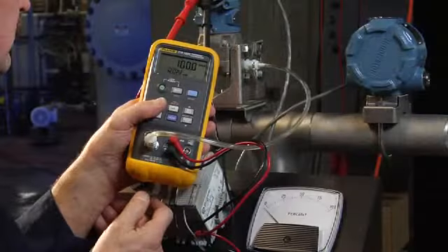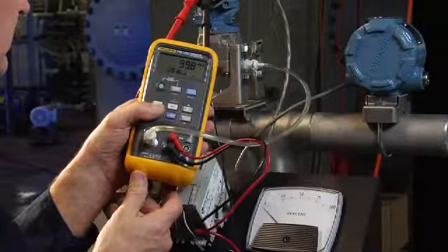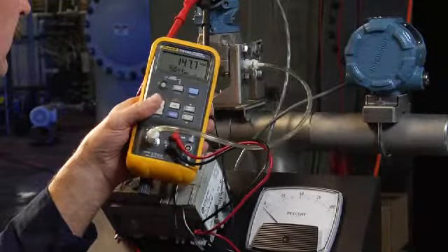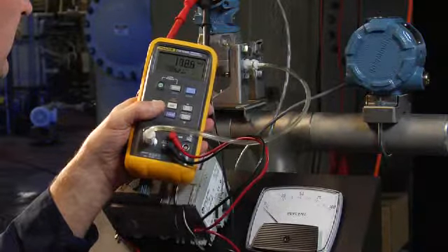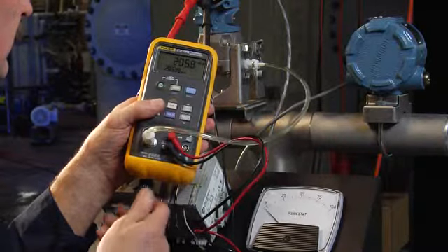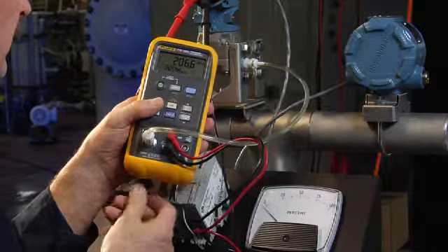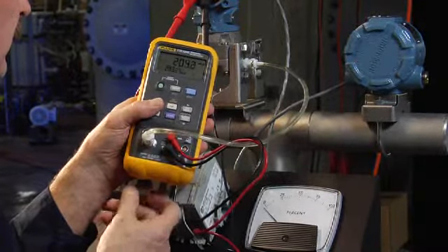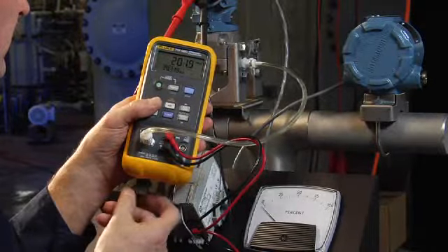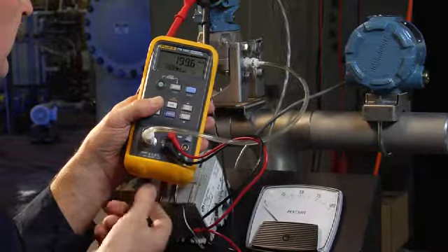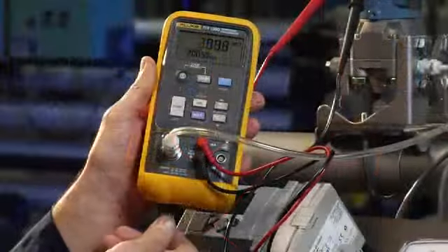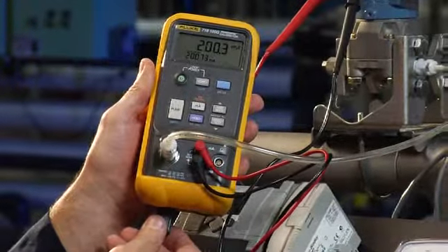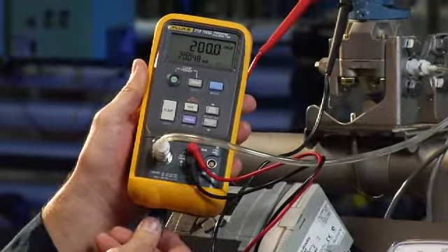The last step is to test the full-scale pressure value of the transmitter, 200 inches of water. Use the electric pump to generate 200 inches of pressure. Use the fine adjust in the pump to dial in the value to exactly 200 inches and verify for 20 milliamps.